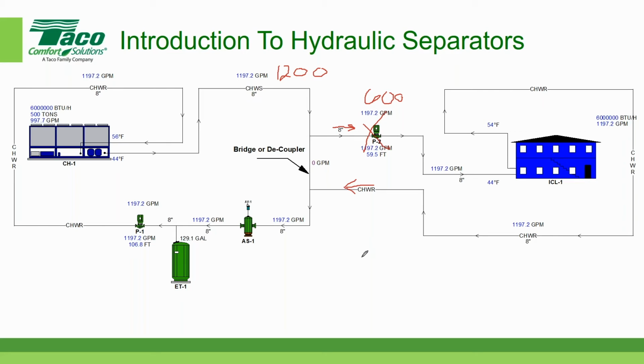Now, our system here, let's assume that our return water temperature happens to be the same. We'll make it 56 degrees over here, just for the fun of it. 56 degrees Fahrenheit. So we have a 12 degree delta T. If we draw off 600 gallons per minute, then what goes across the bridge here is 600 gallons per minute. So we get 600 plus the flow that came back from the secondary loop. We add those two together, 600 plus 600 is 1,200. We're back to 1,200 over here.